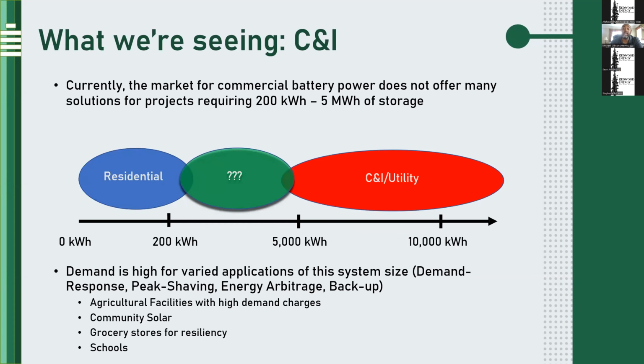What were we seeing in the C&I space? Essentially, there's residential, which we classify around 200 kW of battery storage size. Then utility scale battery storage is usually 5 megawatts, or 5,000 kWh, and above.